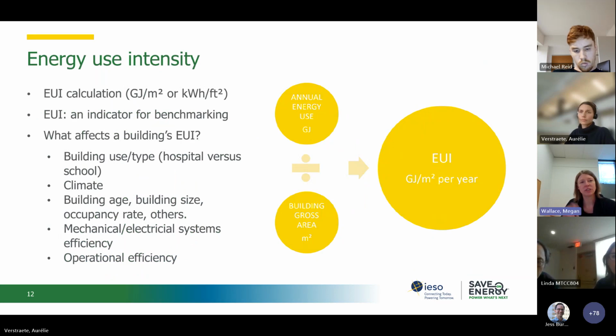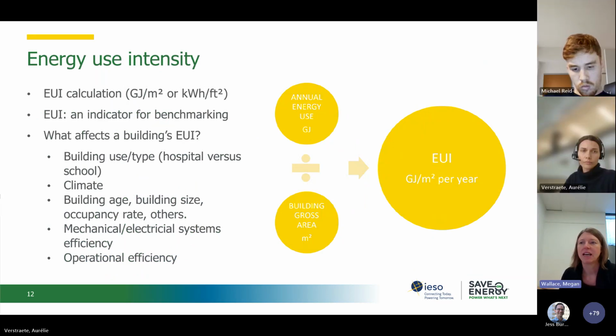One thing referred to earlier was energy use intensity (EUI), expressed as energy per square foot per year. It's calculated by dividing the total energy consumed by the building in one year by its total gross floor area, and it's a key metric to benchmark a building, expressing energy use as a function of its size and characteristics. A low EUI usually signifies good energy performance.